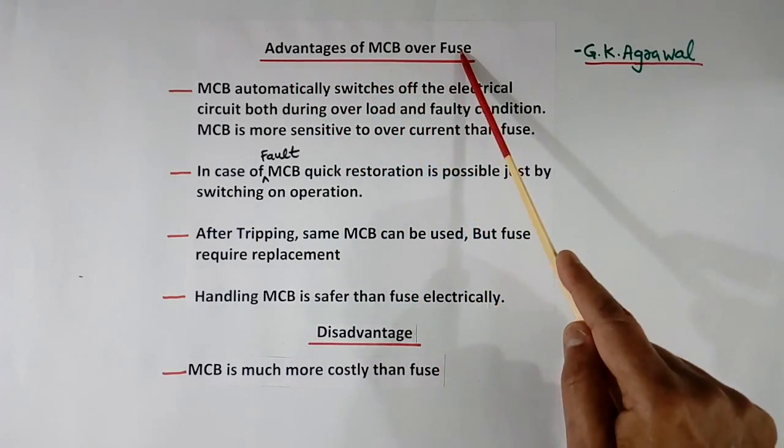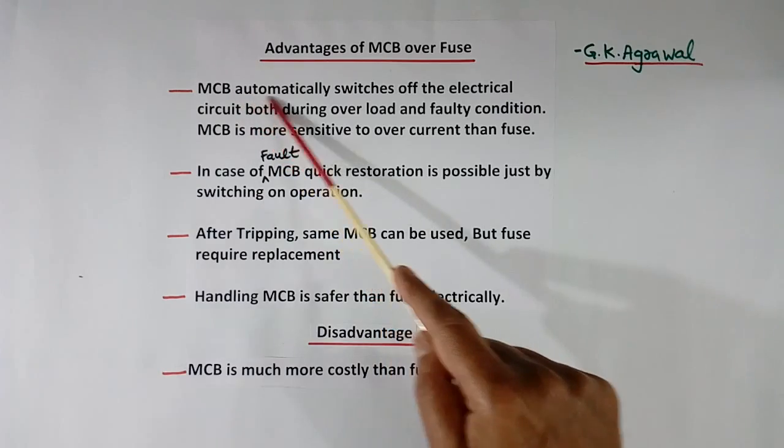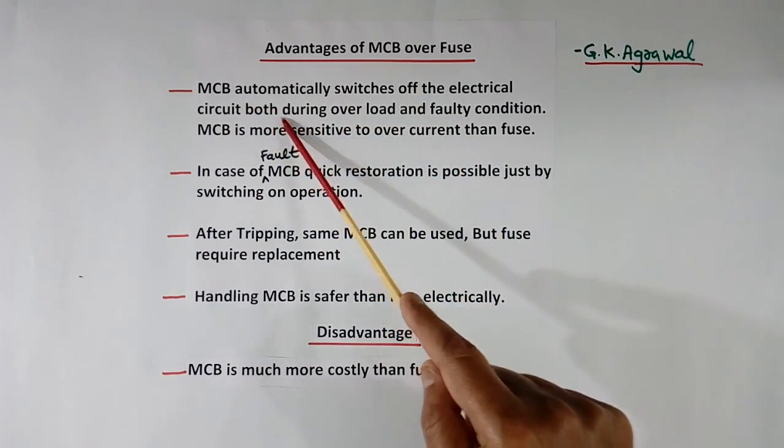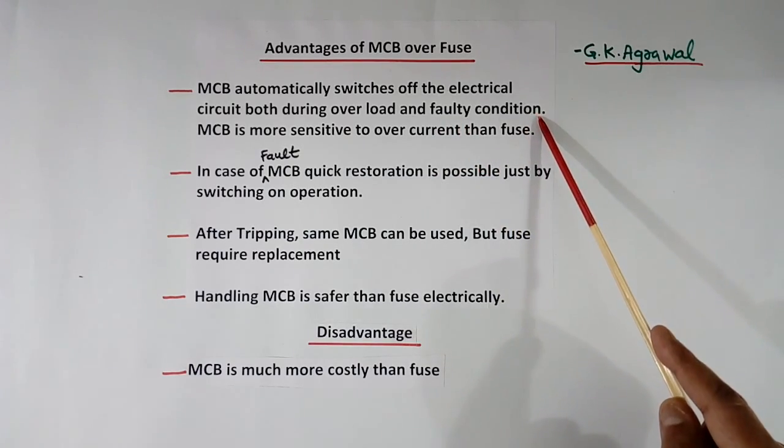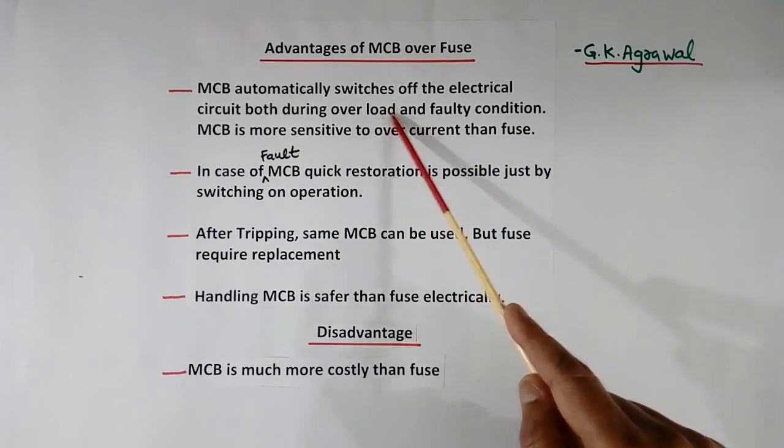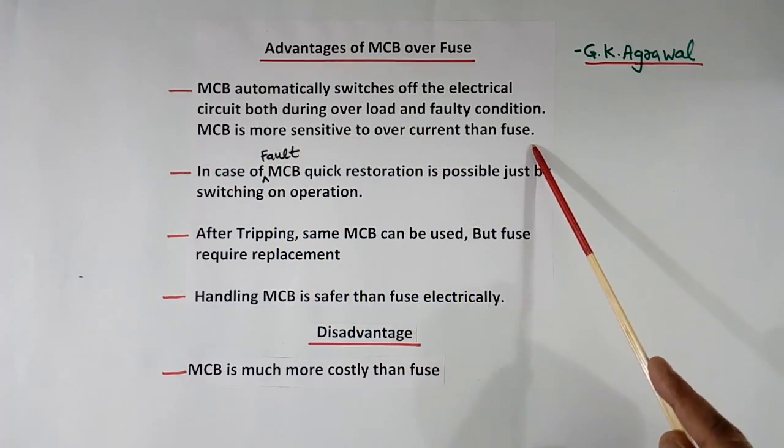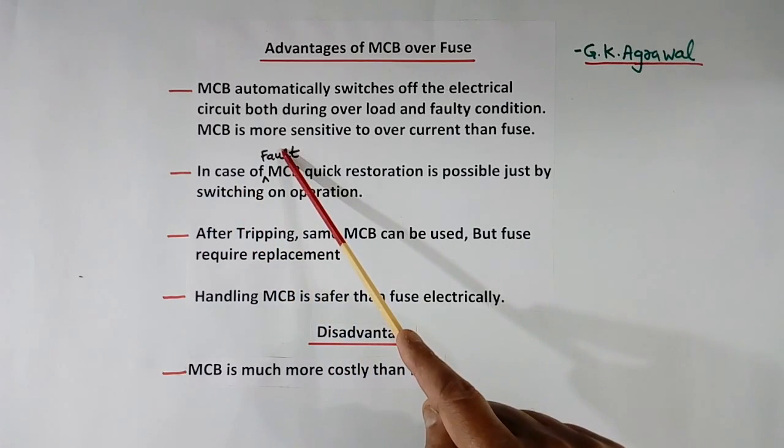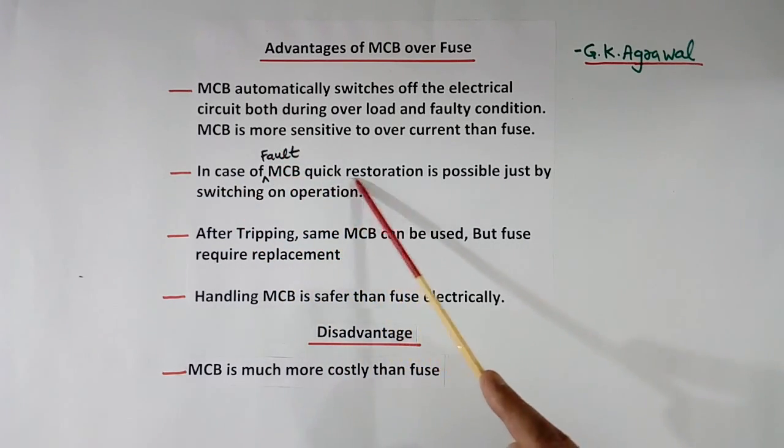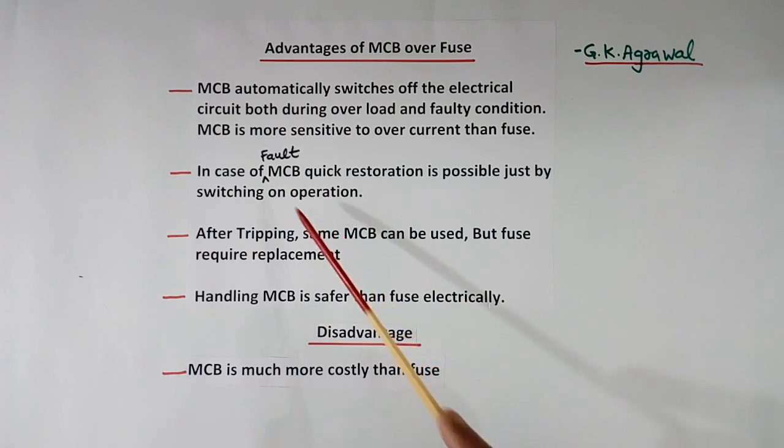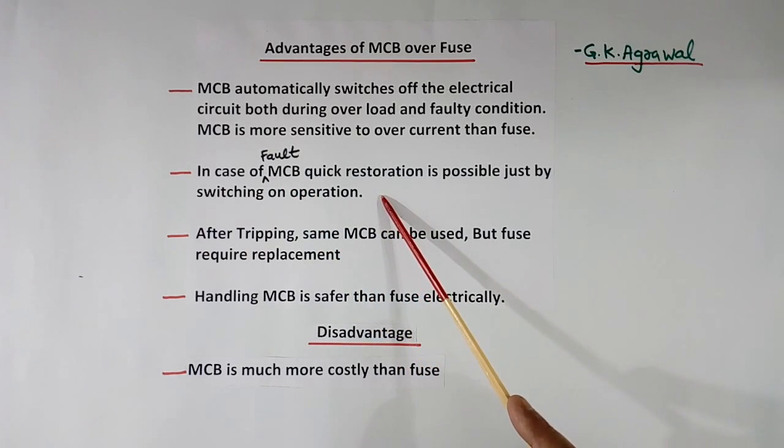Advantages of MCB over fuse: MCB automatically switches off during overload and faulty conditions. Whether it is short circuit or overload, it will automatically switch off. MCB is more sensitive to over-current than fuse. Then in case of fault, MCB will trip, then you can restore quickly by just switching it on. In case of fuses, you will have to replace it. It will take time. Third is, after tripping, this and this are roughly the same. Same MCB can be used, but fuse requires replacement.